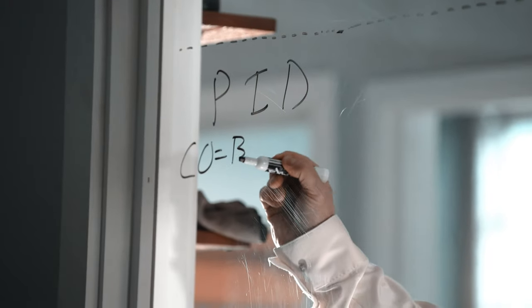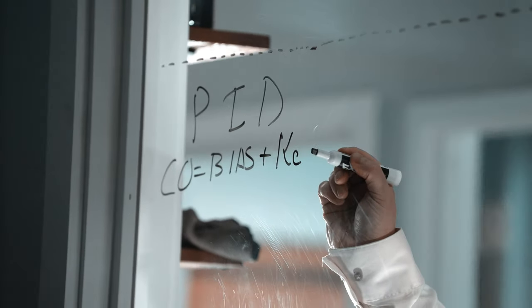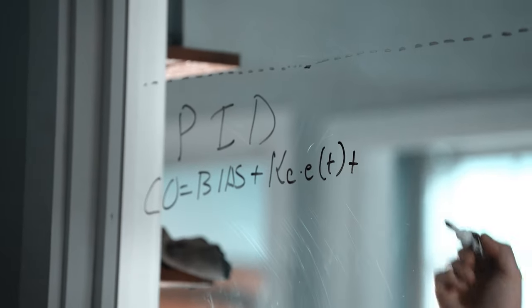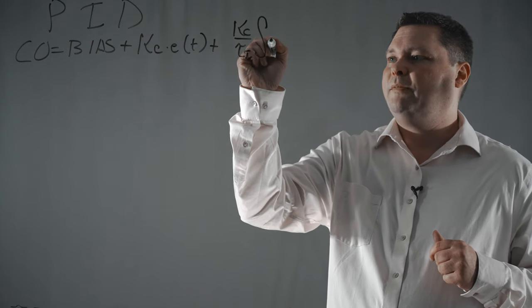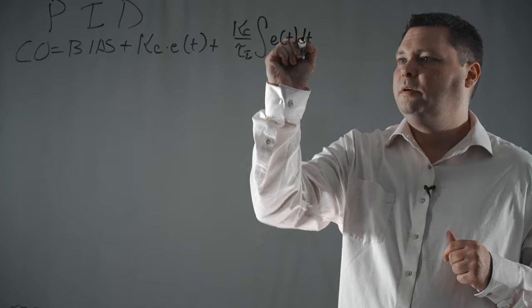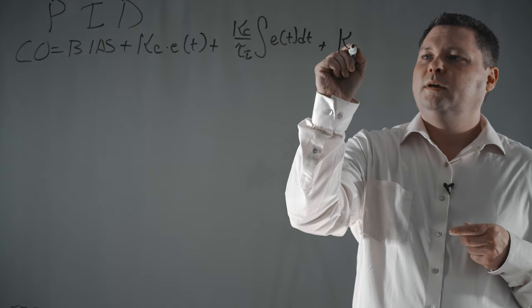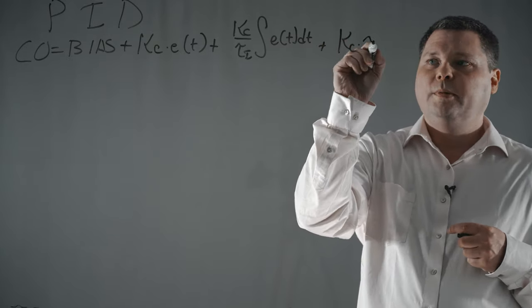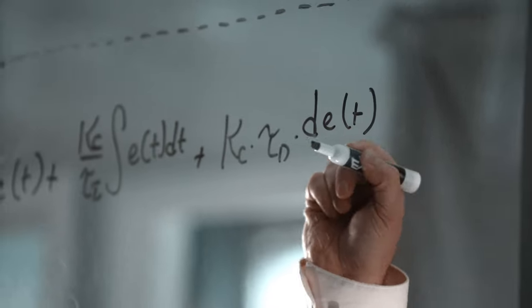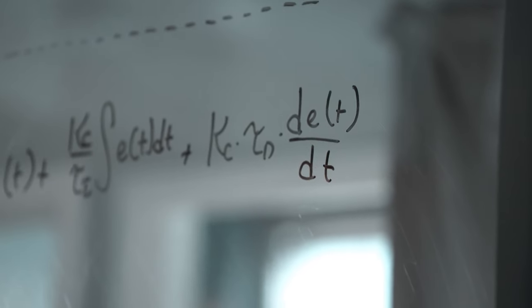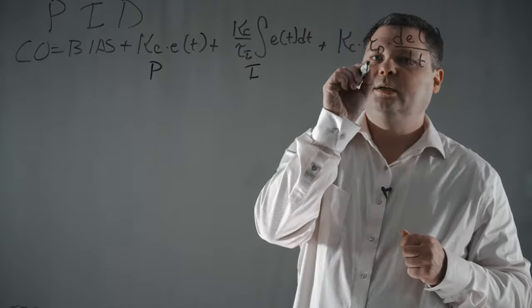We start with the controller output. We add the bias term, which is our starting position. We add our controller gain, which looks at how much error there is. Then we add our integral, which is going to be your controller gain over that reset time parameter. Now we're going to add this new term called derivative. Derivative has a component of the proportional term in it, but it also has this derivative time in there. What we're looking at is the derivative of error, or the change in error. These three components make up the P, I, and D equation.